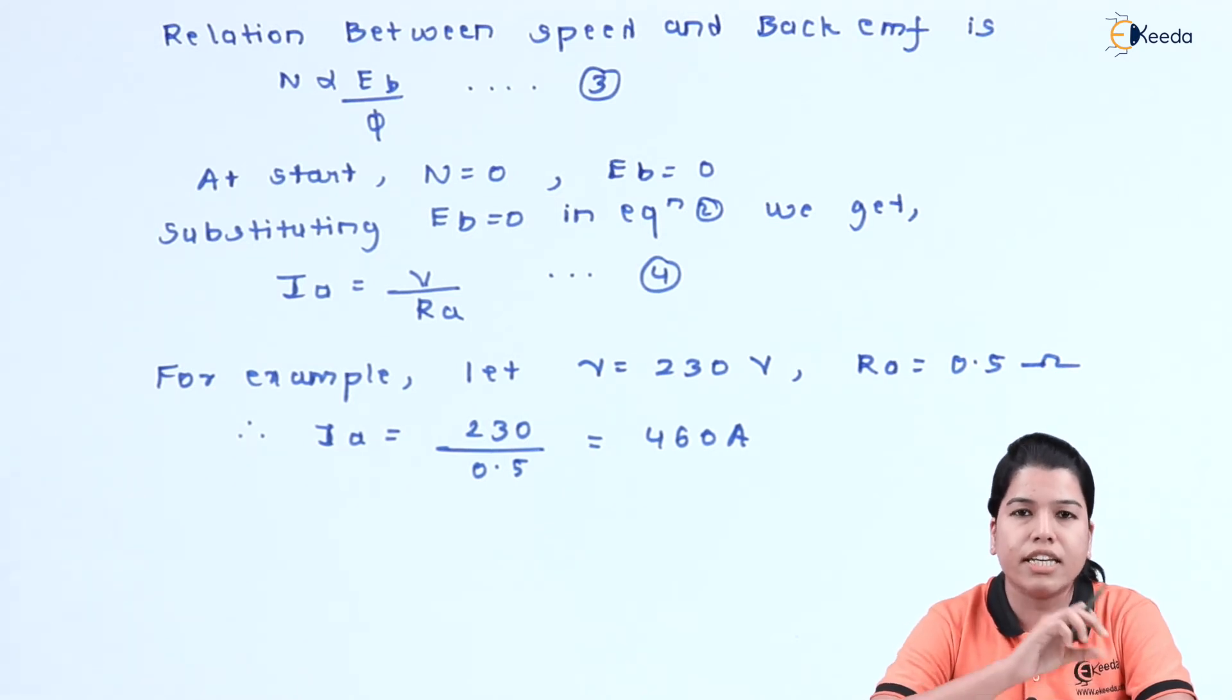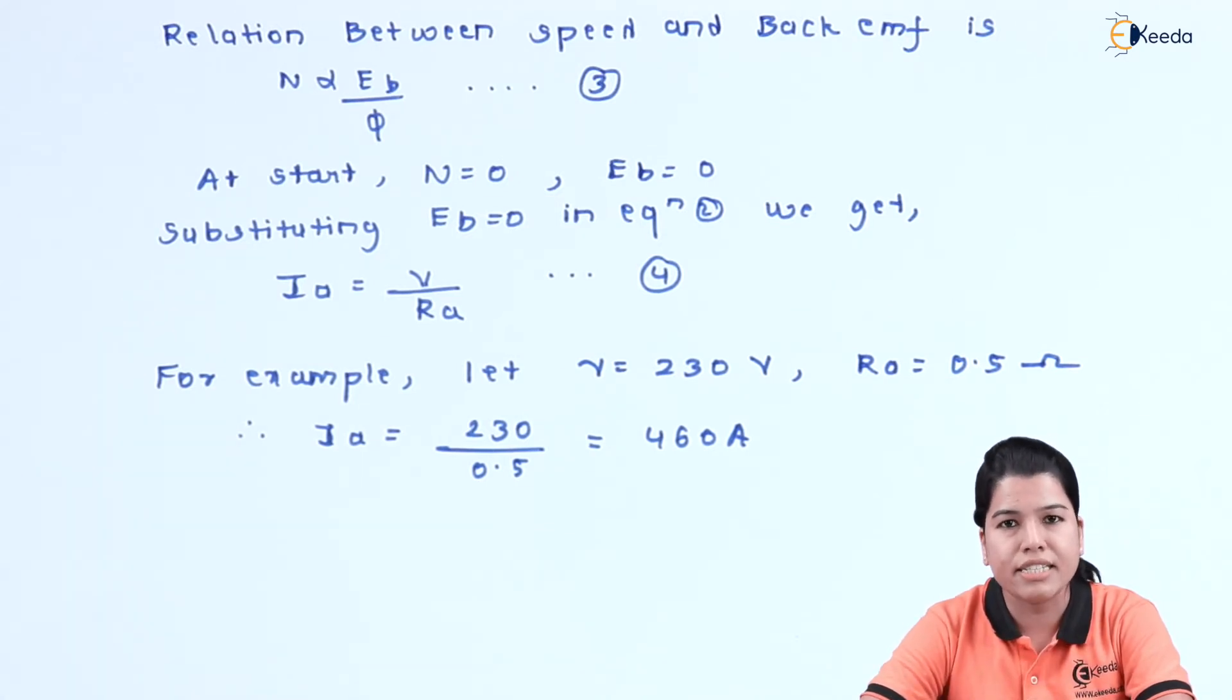For doing this, a series resistance is connected in series with the armature. At starting, the value of resistance is high. As the motor speed goes on increasing, the value is slowly decreased up to it gets the enough speed, and due to this enough speed, the enough amount of back EMF is built up. Once we get the required value of back EMF, the back EMF itself will control the armature current.